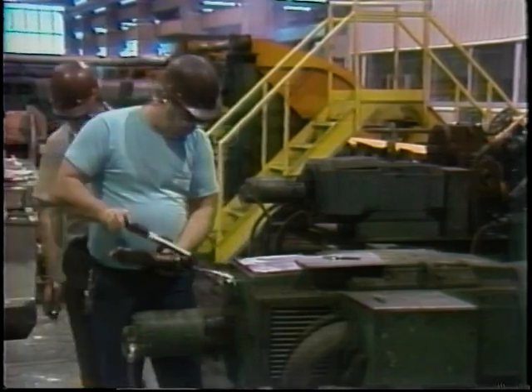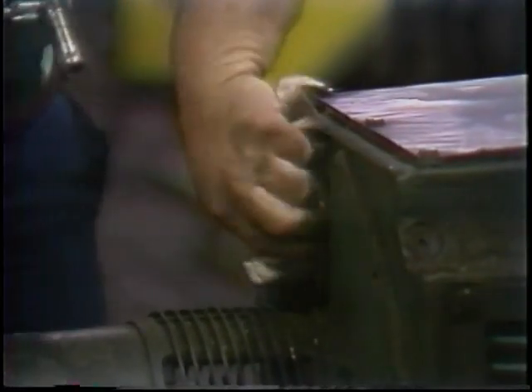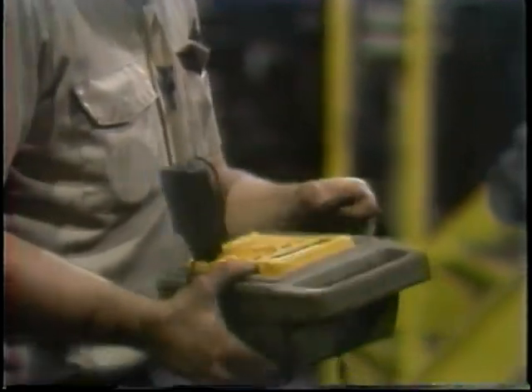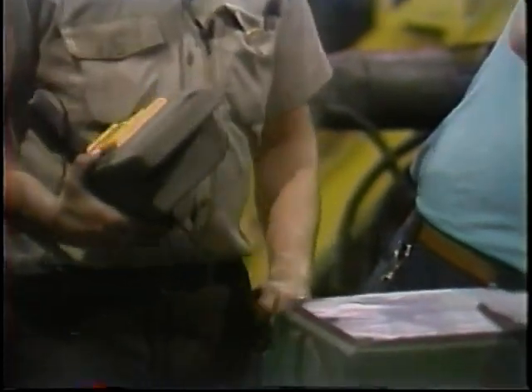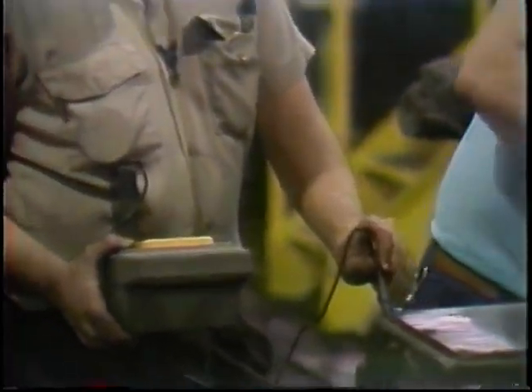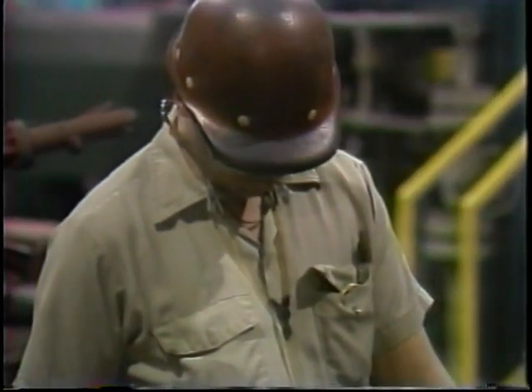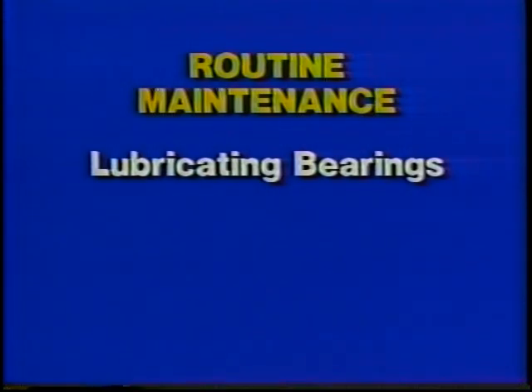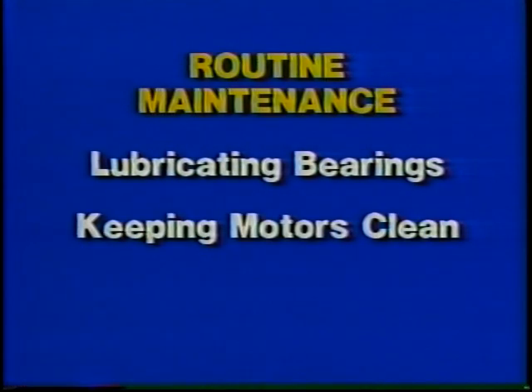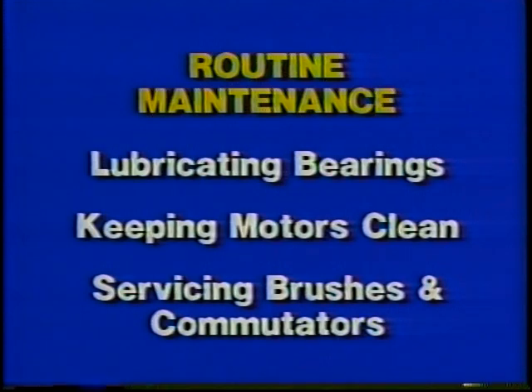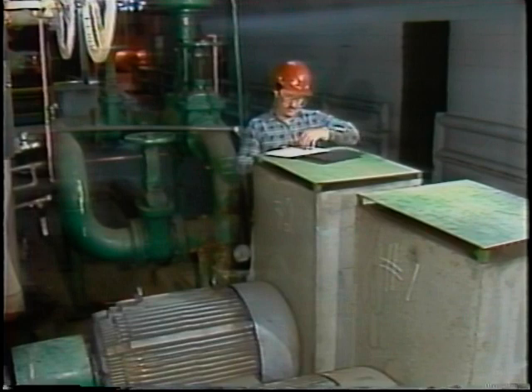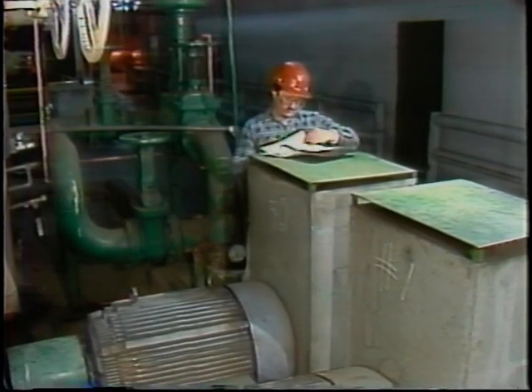So one part of maintenance involves routine tasks which help keep a motor running right. The other part involves inspections and tests to tell if a motor is not running right. Let's look first at typical routine maintenance operations intended to prevent problems from developing. There are three main areas of concern: lubricating bearings, keeping motors clean, and servicing the brushes and commutator on motors which have them. A maintenance schedule for these operations is a useful guide.